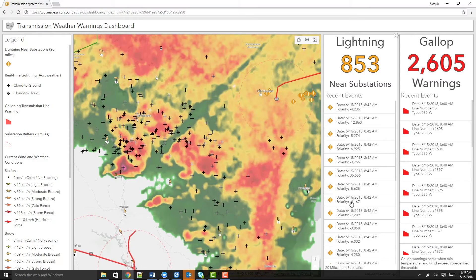The other half of this dashboard is around galloping transmission lines. Galloping is an event where a transmission line becomes covered in ice and then perpendicular winds start to make them gallop or jump rope. This can cause irregular SCADA readings that, without this dashboard, would end up sending costly field workers out for inspection.